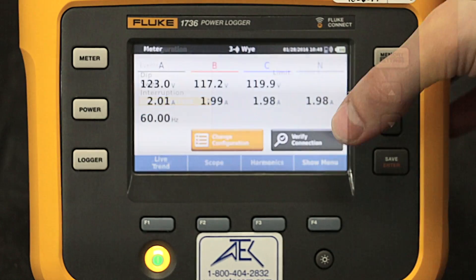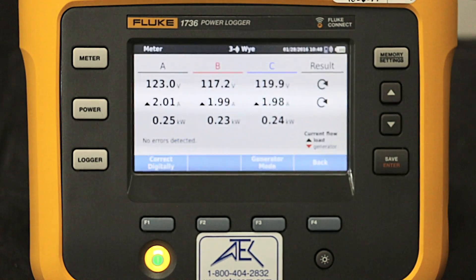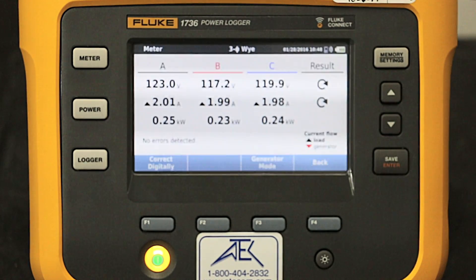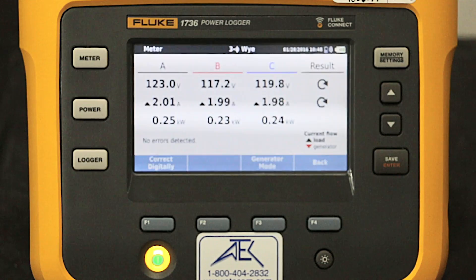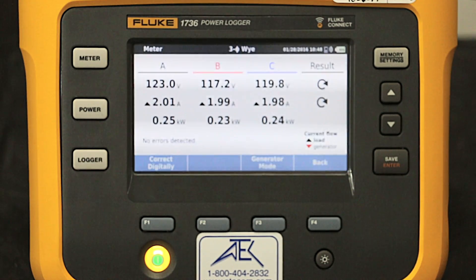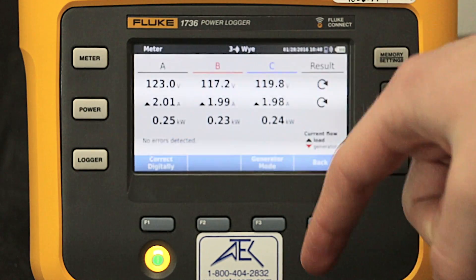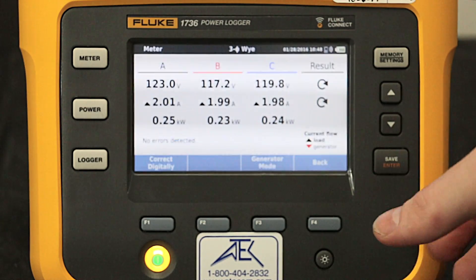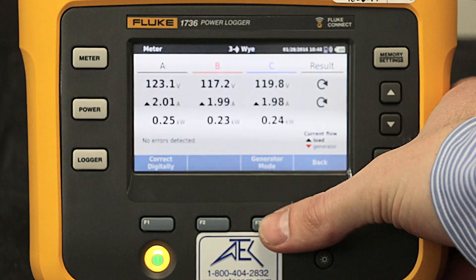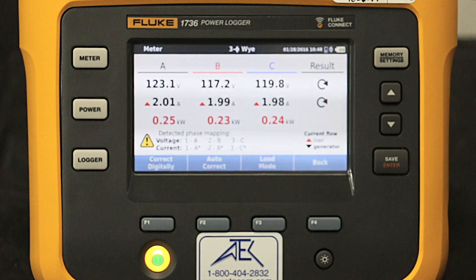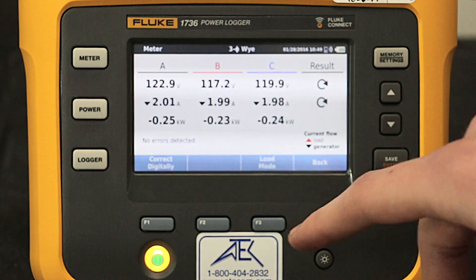Now that we've gone through our configuration, let's check the connection. Here we can see our current measurements, and if your load is on backwards it will be indicated by a red arrow down if it's in generator mode. A red arrow up indicates load mode.